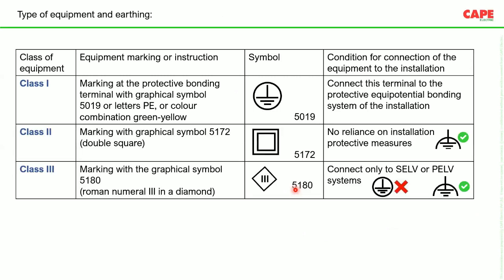When it comes to earthing, one more point you should understand is that electrical appliances are of 3 types. In fact, there are 4 types. Class 0 is also there, but nowadays class 0 is banned. So basically, electrical appliances are classified into class 1, class 2, and class 3 appliances. Class 1 devices require protective earthing. Class 2 devices are basically devices with a 2-pin plug. Protective earthing is not necessary, but sometimes functional earthing is required.